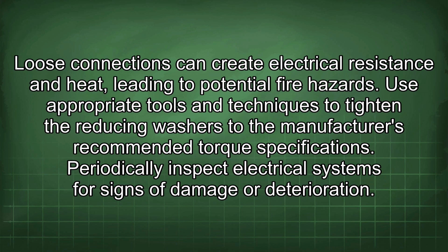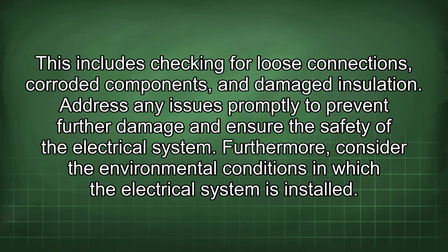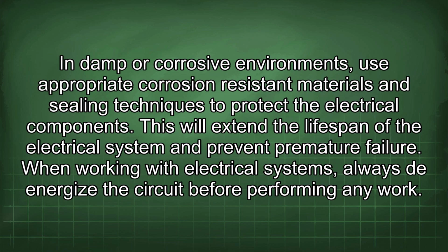Periodically inspect electrical systems for signs of damage or deterioration. This includes checking for loose connections, corroded components, and damaged insulation. Address any issues promptly to prevent further damage and ensure the safety of the electrical system. Furthermore, consider the environmental conditions in which the electrical system is installed. In damp or corrosive environments, use appropriate corrosion-resistant materials and sealing techniques to protect the electrical components. This will extend the lifespan of the electrical system and prevent premature failure.